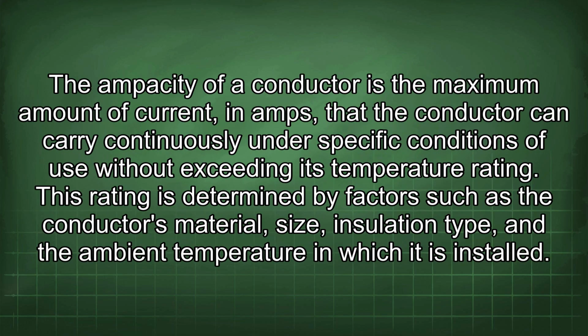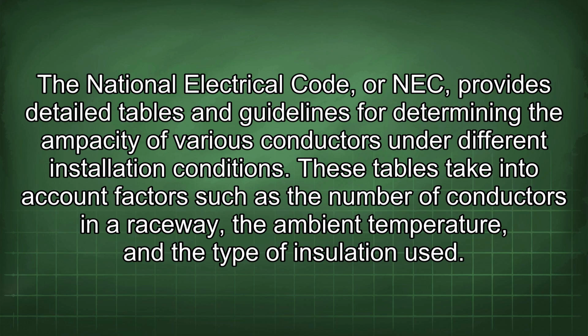The ampacity of a conductor is the maximum amount of current, in amps, that the conductor can carry continuously under specific conditions of use without exceeding its temperature rating. This rating is determined by factors such as the conductor's material, size, insulation type, and the ambient temperature in which it is installed. The National Electrical Code, or NEC, provides detailed tables and guidelines for determining the ampacity of various conductors under different installation conditions.